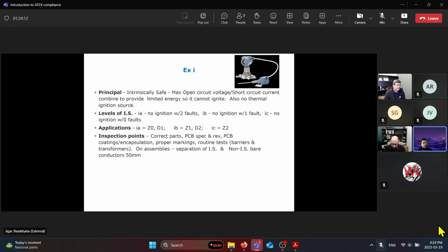If it's for zone 1, then for no ignition with 1 countable fault. And if it's for zone 2, we would just test the product with no countable faults applied to the product. So this would be something that you would have to give us designed with countable faults, at least during the testing phase of the product, if this is something you consider. And the applications, like I said, you can use this in zone 0, division 1, zone 1, division 2, as well as zone 2, as well as zone 20, 21, 22. It's applicable to both gas and dust environments.